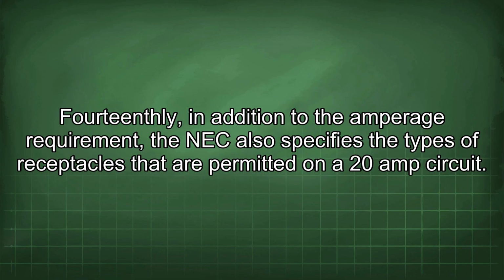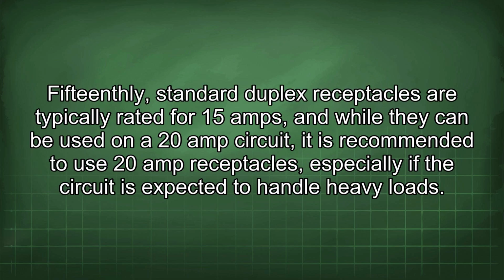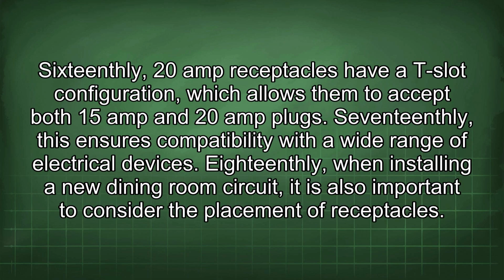Fourteenthly, in addition to the amperage requirement, the NEC also specifies the types of receptacles that are permitted on a 20 amp circuit. Fifteenthly, standard duplex receptacles are typically rated for 15 amps, and while they can be used on a 20 amp circuit, it is recommended to use 20 amp receptacles, especially if the circuit is expected to handle heavy loads. Sixteenthly, 20 amp receptacles have a T-slot configuration, which allows them to accept both 15 amp and 20 amp plugs.